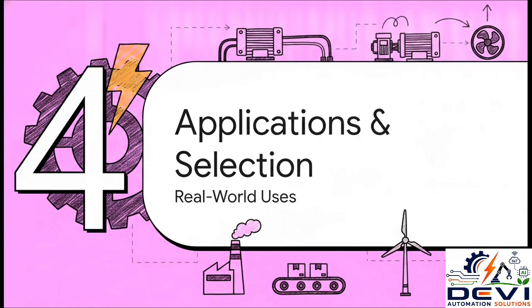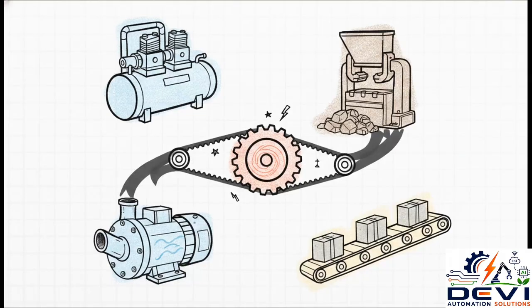Let's talk real-world uses. The sources point out that if your factory really only needs to get a heavy load moving smoothly and then let it run at a fixed speed all day long, the soft starter is your clear winner. Think about massive air compressors, rock crushers in a cement plant, basic water transfer pumps, or heavy conveyor systems. I mean, you don't actually need to vary the speed of a rock crusher while it's crushing rocks, right?